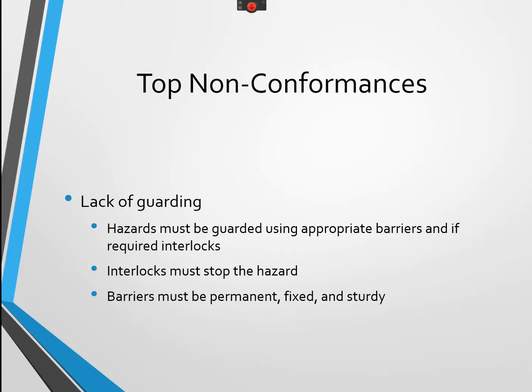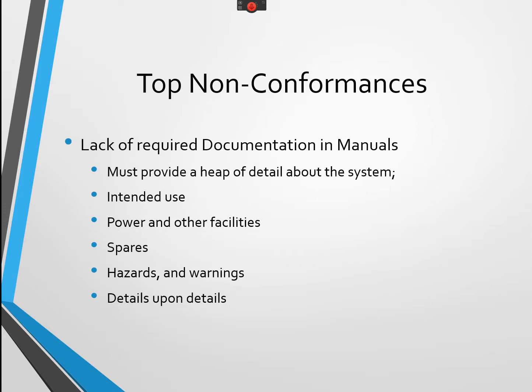Barriers must be permanent, fixed, and sturdy. And in some cases, we see people using polycarbonate, clear, see-through barriers. That's fine so long as they have enough strength and that they're built of a flame retardant material, and we need to be able to prove that. Lack of documentation in the manuals. One we were just talking about just before I started this video was the labels weren't recreated in the manuals, and the warnings for hazards were not recreated in the manuals next to each process, procedure, service procedure that created a hazard. So we need to be sure that you have that.